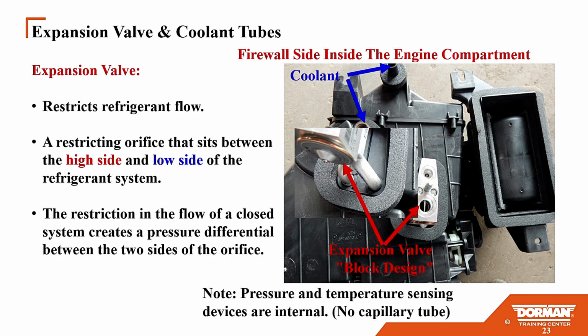We'll get into that a little bit. You've got a high and low side of the refrigerant system. So the restriction of flow in a closed system creates, and that's the whole idea, trying to create a pressure differential between the two sides of the orifice. It's just like pulling your water nozzle, you make a difference in how much pressure is coming out, more or less. And always keep in mind that there's a pressure and temperature sensing device internal, but there is a relationship between pressures and temperatures, okay? Typically you have other ones that have a capillary tube, so they do come somewhat in different configurations, okay.